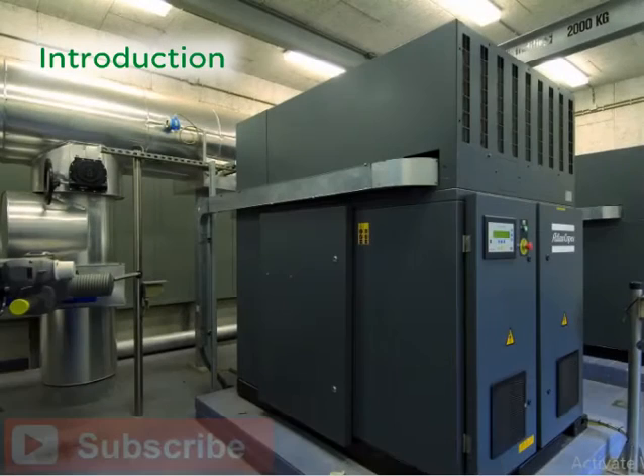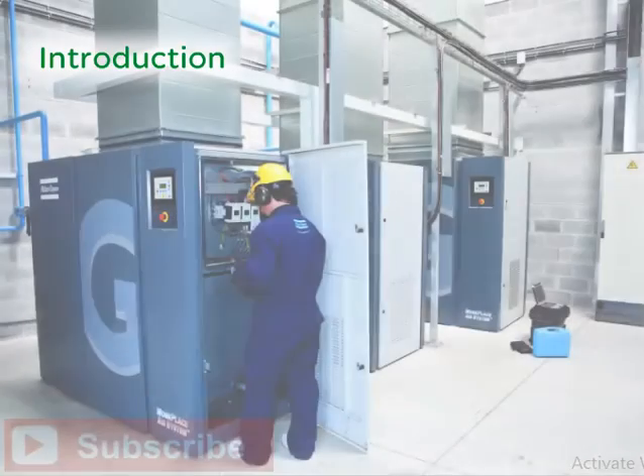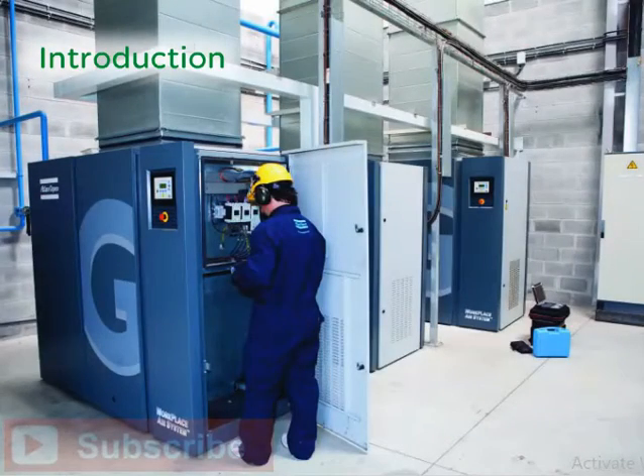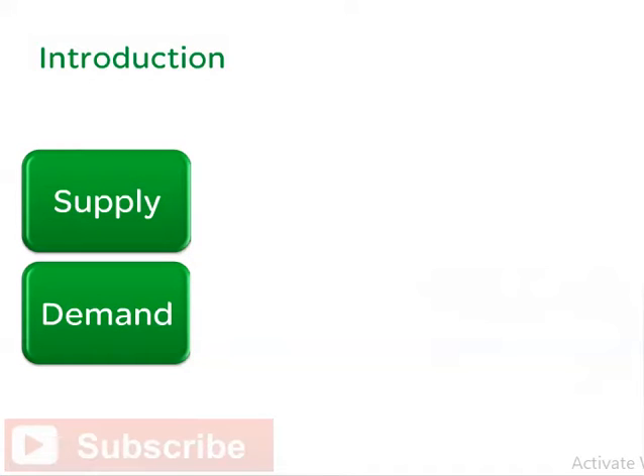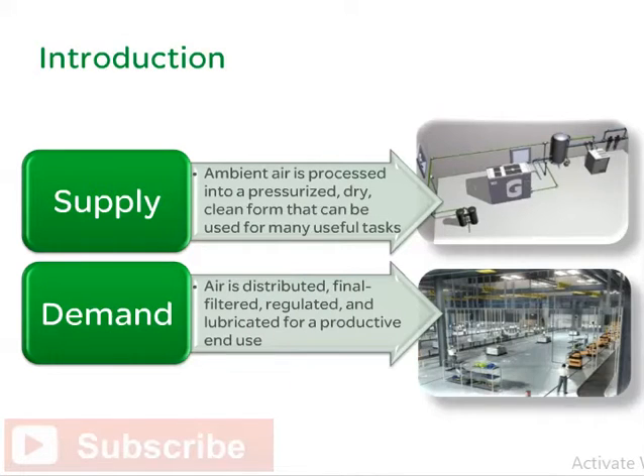Compressed air system components can usually be identified by the major function that they provide, whether the function is related to compression, conditioning, filtration, distribution, and some nature of end use. Most systems have a supply side and a demand side. The supply side is normally where ambient air is processed into a pressurized, dry, clean form that can be used for many useful tasks. The demand side is the portion of the plant where air is distributed, final filtered, regulated, and perhaps lubricated for a productive end use. The images in this slide depict both the supply side and the demand side of a typical industrial compressed air system.